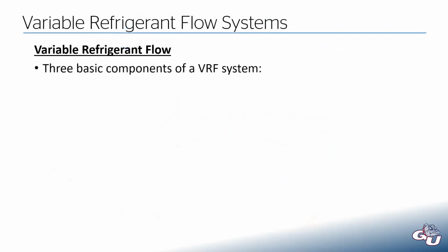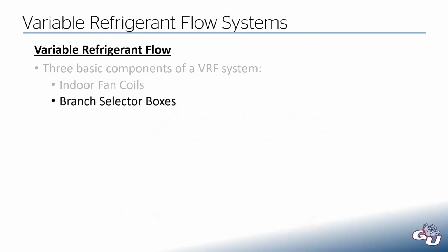So there are 3 basic components of a VRF system. You have your indoor fan coils, and I'll talk about each of these in more depth here in a second. You have your branch selector boxes. Sometimes they're called branch controllers. There's even a third term that I'm blanking on right now. Every manufacturer has their own term for it. And then you have your outdoor heat pumps.